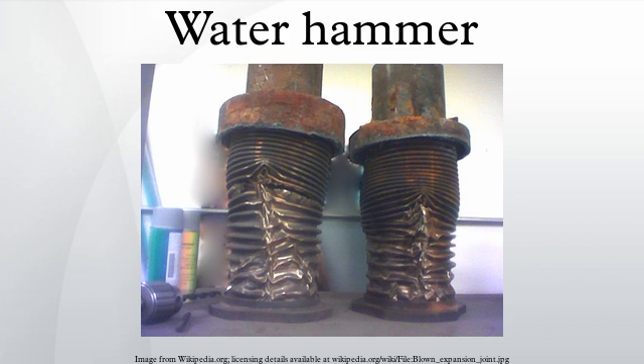When the time it takes a valve to close is long compared to the propagation time for a pressure wave to travel the length of the pipe, then rigid column theory is appropriate. Otherwise, considering elasticity may be necessary. Below are two approximations for the peak pressure, one that considers elasticity, but assumes the valve closes instantaneously, and a second that neglects elasticity but includes a finite time for the valve to close.